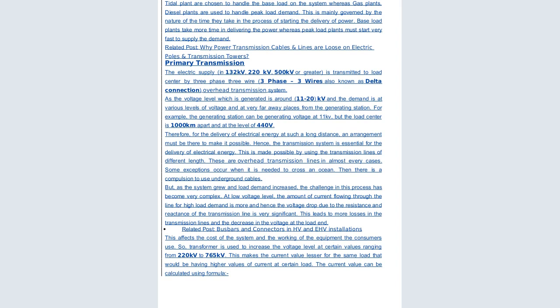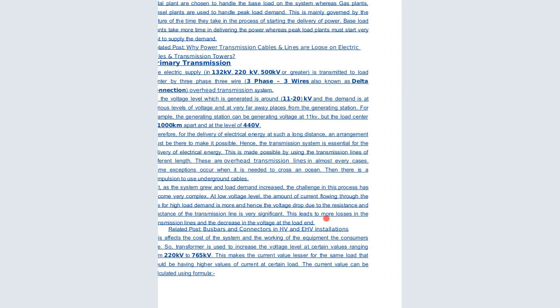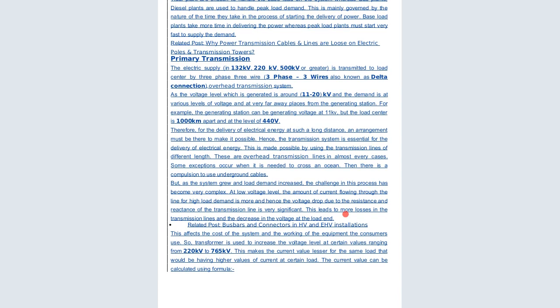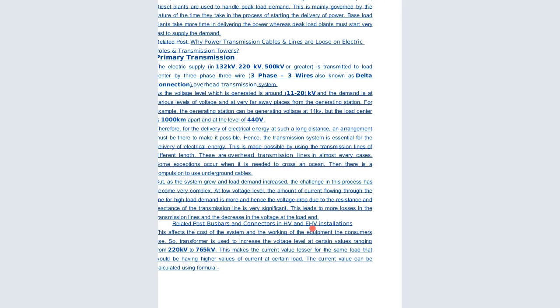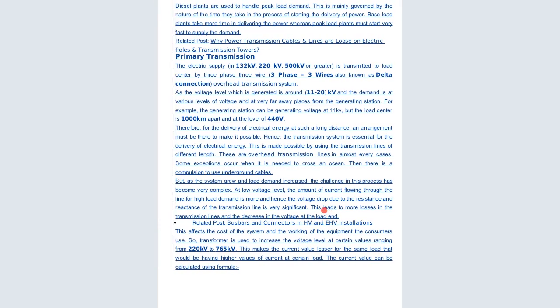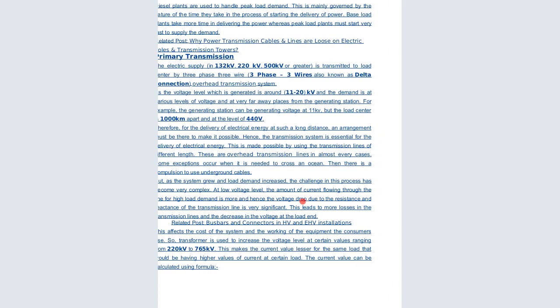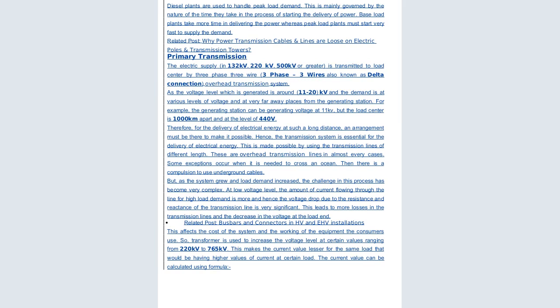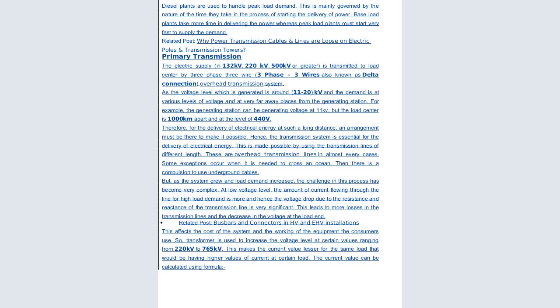The primary transmission, that is the electric supply of 132 kilovolts, is transmitted to load centers by three-phase, three-wire, delta-connected overhead transmission. The voltage level is generated at around 11 kV, and the demand is at various levels of voltage and at places very far away from the generating station. For example, the generating station can be generating at 11 kilovolts, but the load center is far apart from that. Therefore, for the delivery of electrical energy over such a long distance, an arrangement must be there to make it possible. Hence, the transmission system is essential for the delivery of electrical energy. This is made possible by using transmission lines of different lengths. These are overhead transmission lines in most cases.